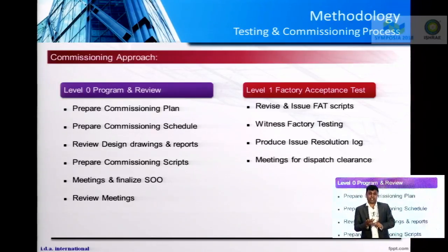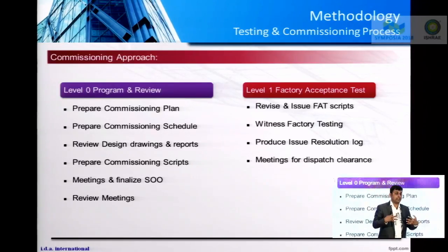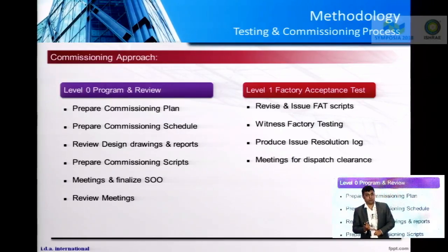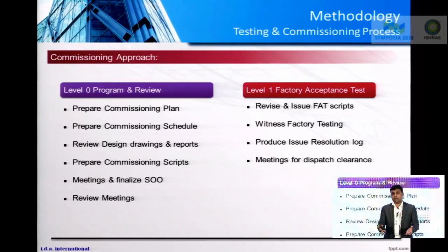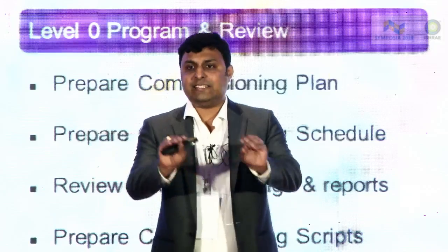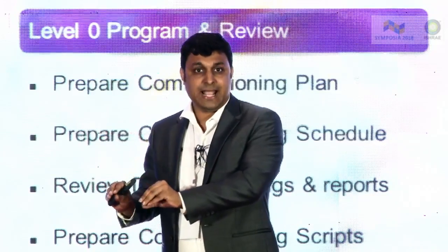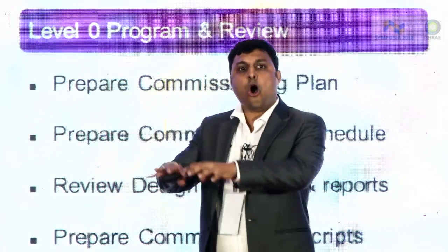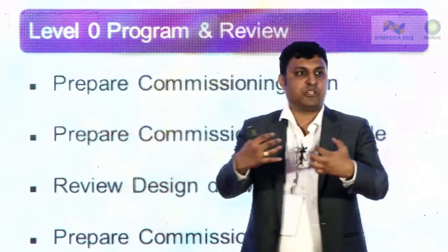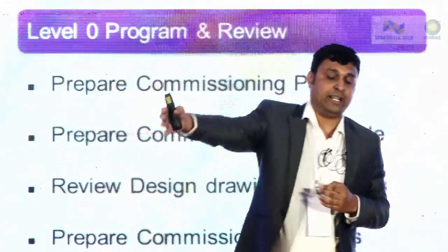The first thing we have to ensure is that the design captures all the commissioning requirements. Like, you have the right number of load bank breakers, you have the right size of load bank breakers, you have allocated a space for the load bank, you have the right amount of balancing valves, a right amount of chill water test points. All these are related to commissioning points, and we have to ensure that all these commissioning requirements are captured in the design. So you don't have to wait till the construction starts, you can take care of this right at the design stage.